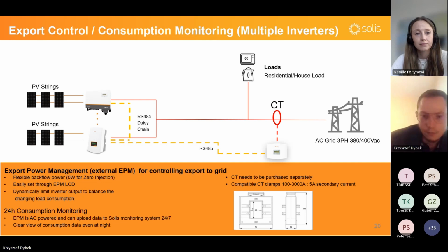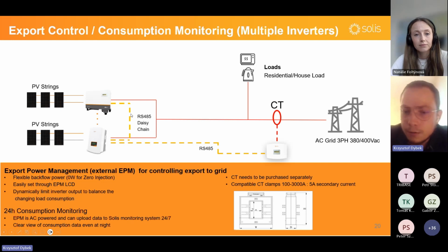COM ports. This is also important if you use RS485 daisy chain. So up to 20 kilowatts, our inverters, we use 4 pin plugs, but starting with 30 kilowatts and above, we have more options. Terminal block or RJ45 plug as well.